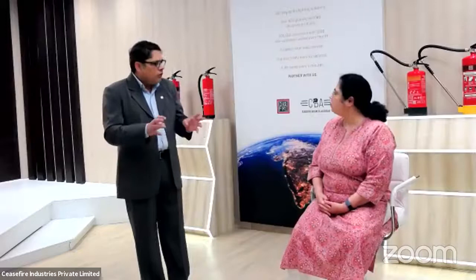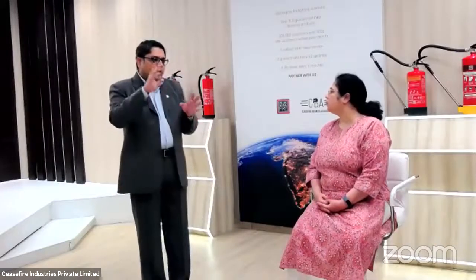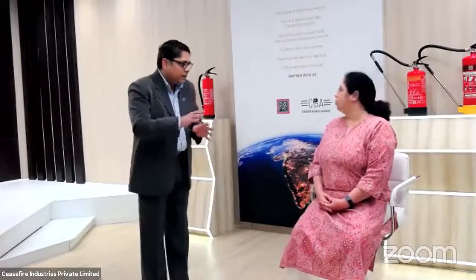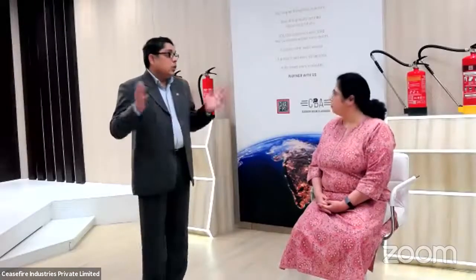Yes, mostly what my concern, or any design person's concern, would be is to have the correct size of the agent cylinder, where we are doing an LPS 1666 certified system, which is up to 2 cubic meters. Now, what happens is I don't want to use a great amount of agent until there's quite a large opening to have a consistent volume within the enclosure.